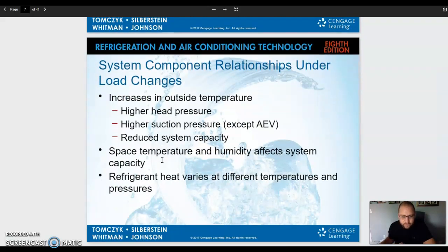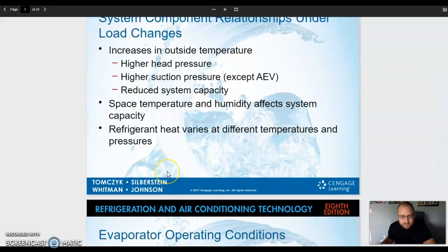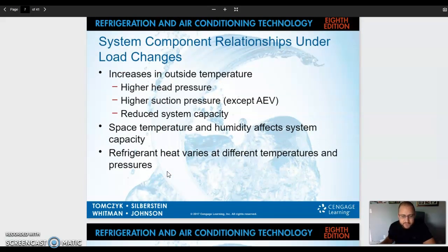So we get this rule that you're going to hear me say a lot, and you can write this down. Indoor minus 30, outdoor plus 20. That's a very general rule. It's not the be all end all, but it does get you in the ballpark. And sometimes you'll see it indoor minus 35.